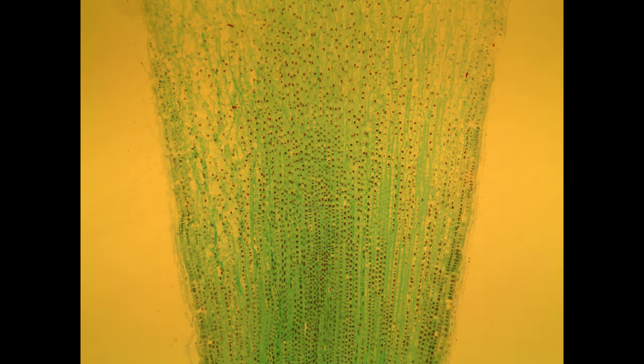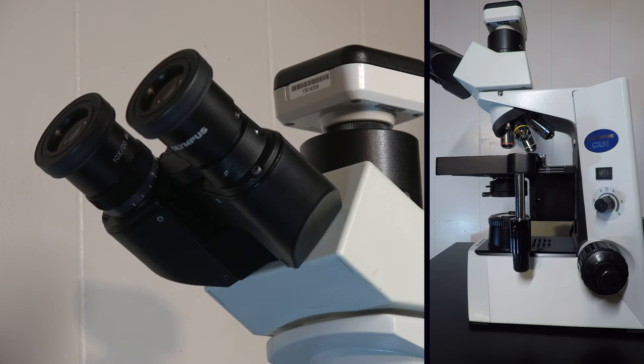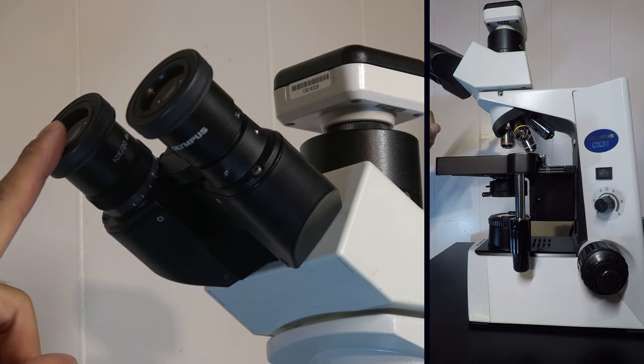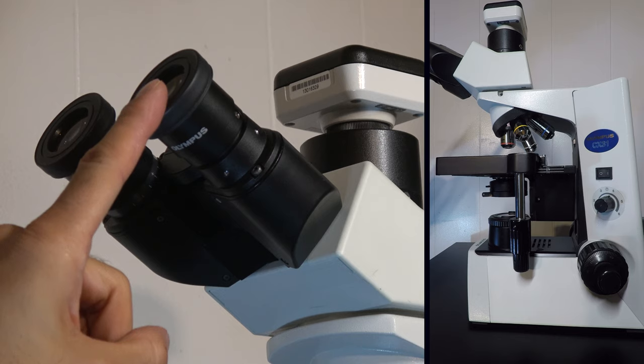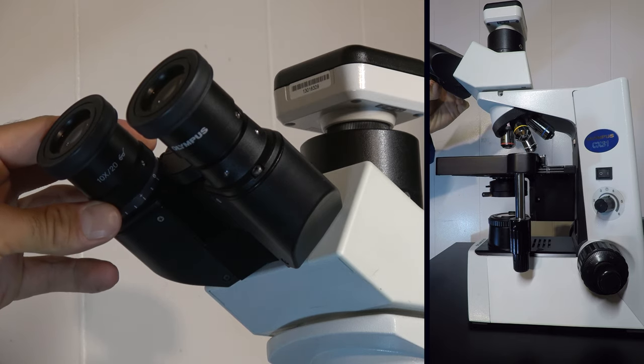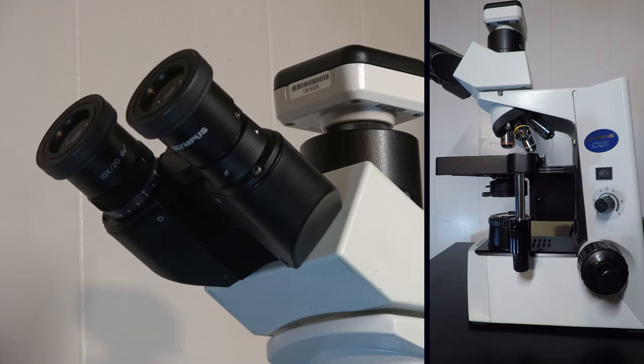Next, we should tune the scope to correct for differences in acuity between each of your eyes. On this scope, we would close our left eye and get the image into focus on the right eye using the fine focus knob. Then close the right eye and rotate the left eyepiece so that your view through the ocular is focused.